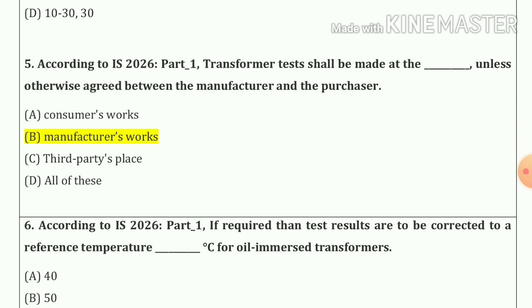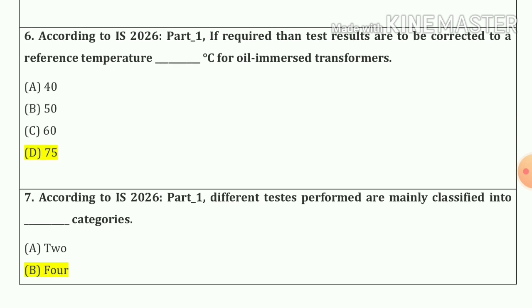Now question number 5. According to IS 2026 Part 1, transformer test shall be made at blank unless otherwise agreed between the manufacturers and the purchaser. So our answer is option number B, manufacturer's work. Question number 6. According to IS 2026 Part 1, if required then test results are to be corrected to a reference temperature 75 degrees Celsius for oil immersed transformer. So our answer is 75, option number D.